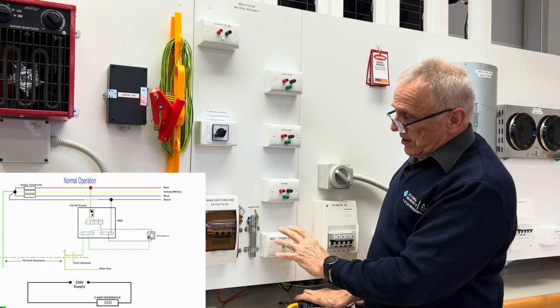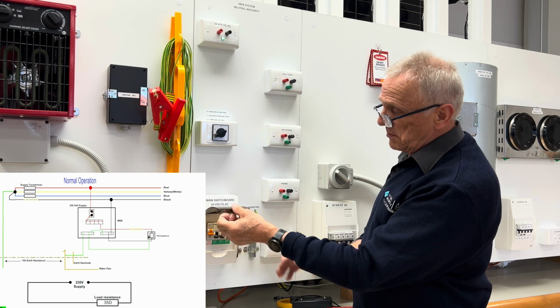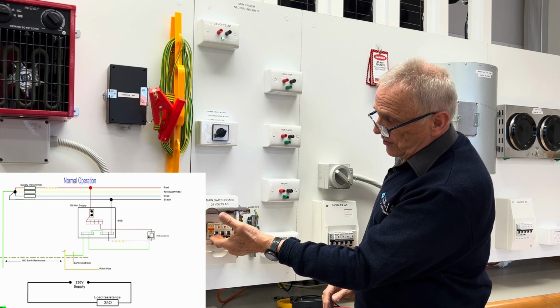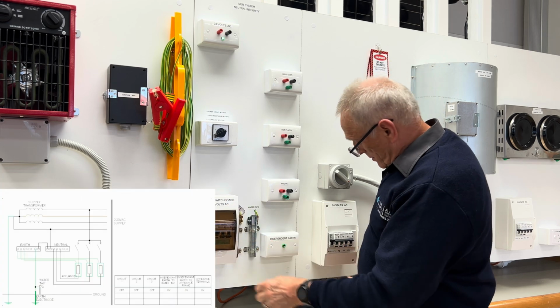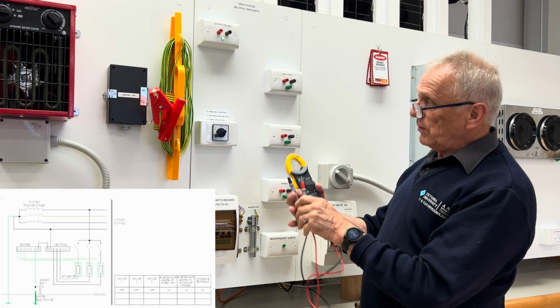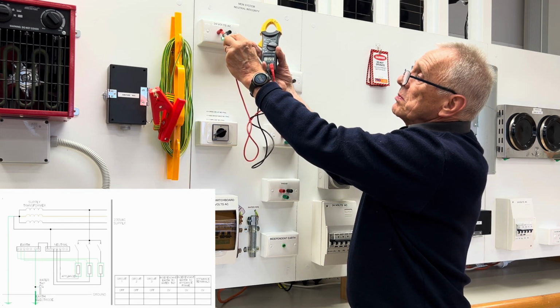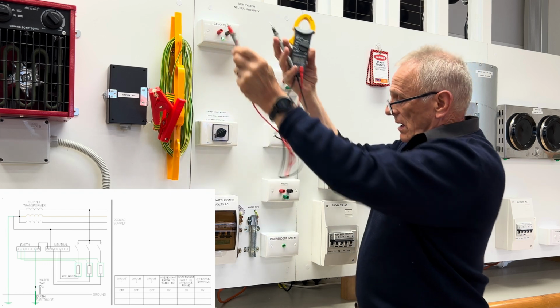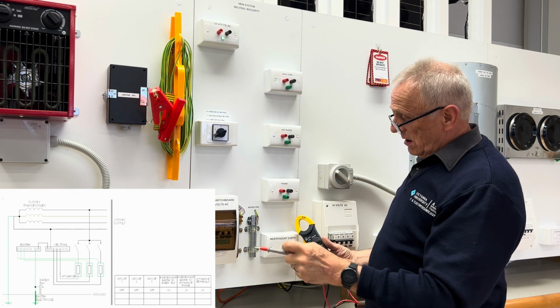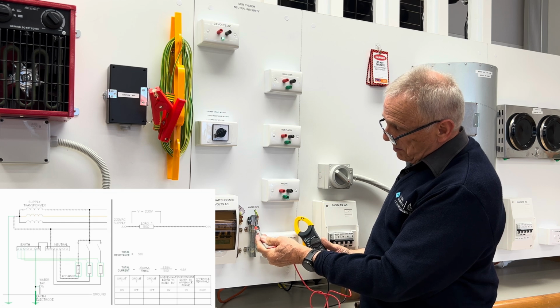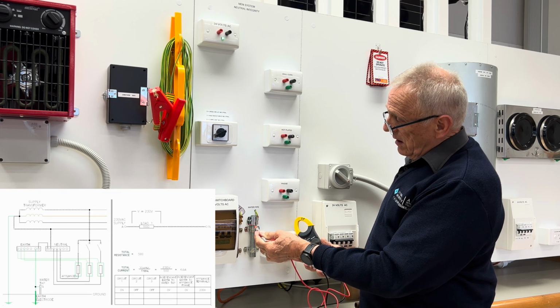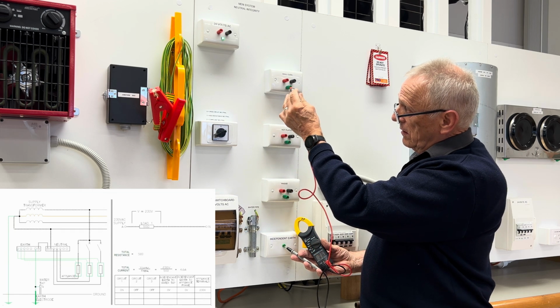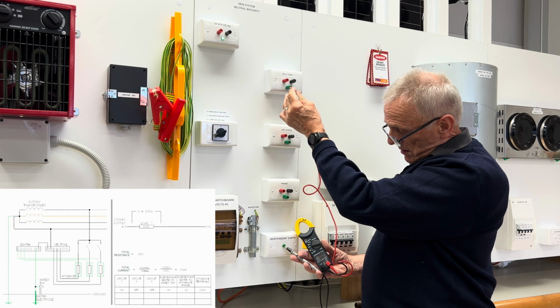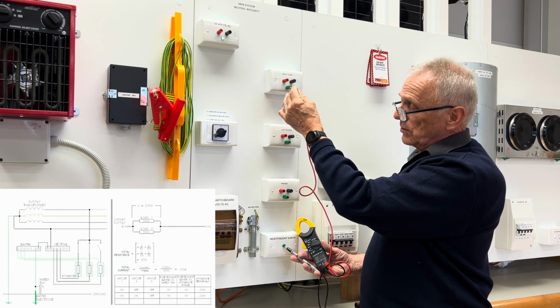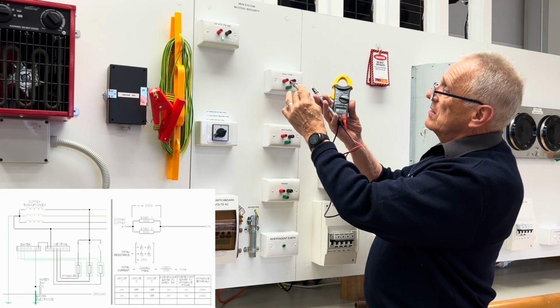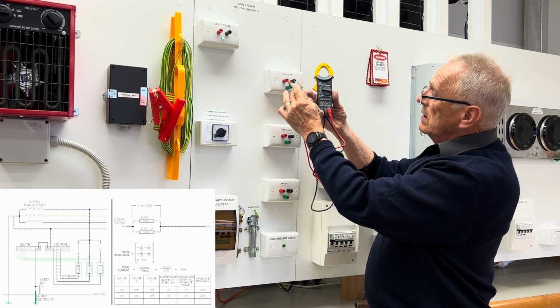We'll be using the independent earth, and the first procedure is to turn the main switch on and the first circuit breaker, the wall oven. Now, we start with the supply, incoming supply, 24 volts. And then we use our independent earth, and we test then the water pipe, or the earthing system of the water pipe, and the actual frame of the wall oven. And in both cases there are 0 volts on those 2 points. Then we test the supply at the wall oven, which should be 24 volts.